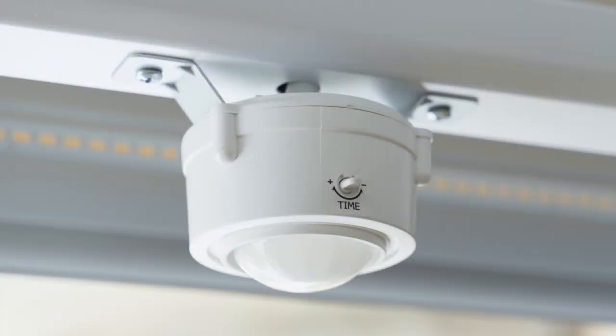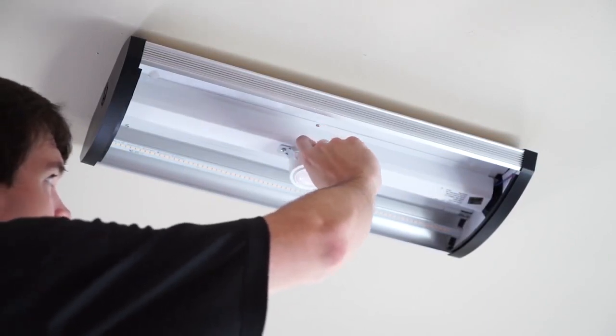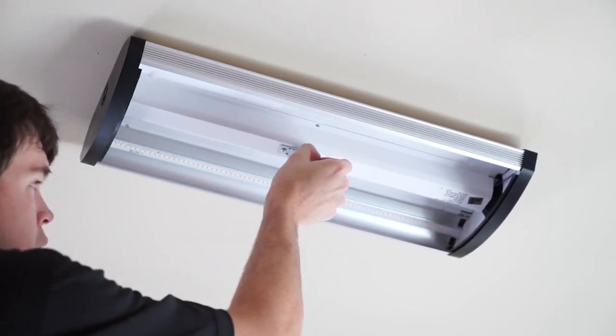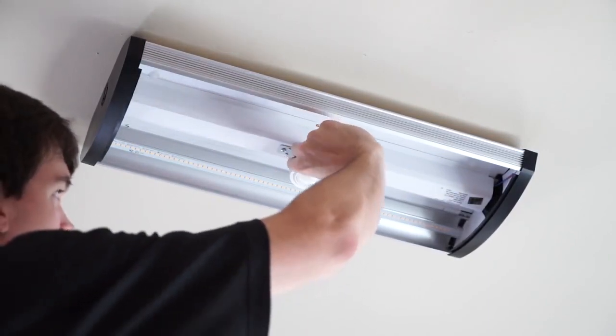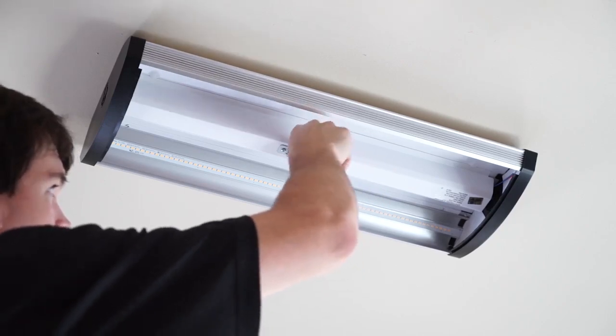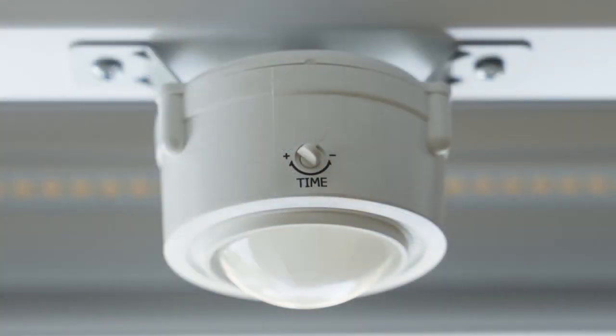Prior to reinstalling the diffuser, adjust the time delay on the PIR sensor to your desired settings. Maximum delay time is 10 minutes and minimum is 1 minute. To increase the amount of time the fixture will remain illuminated, rotate the knob toward the plus symbol.